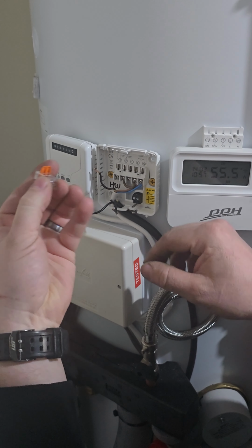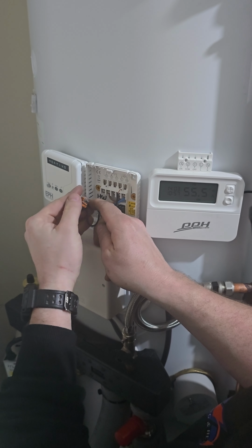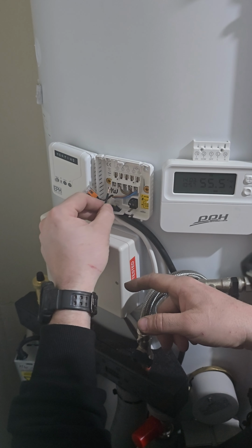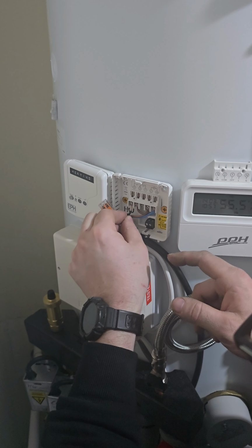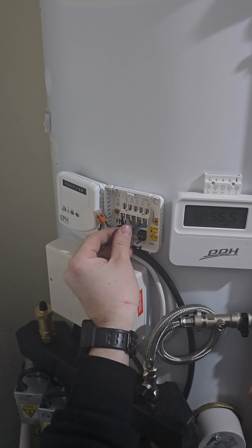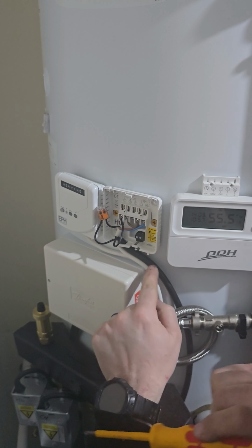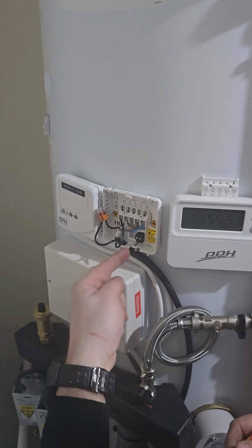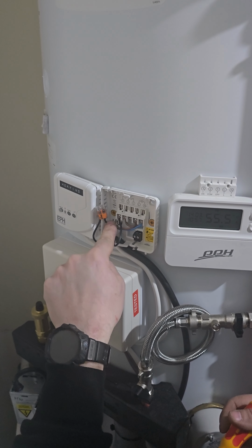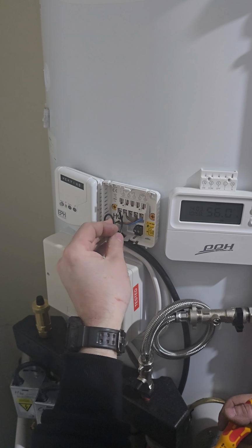So we're just going to get ourselves a cheeky little plumber's push fit, Sparky's push fit, their equivalent, and we're going to link the high limit stat to the switch live out, right, and then we're going to replace the power from the high limit stat back to this. So if the high limit stat activates, even though it's sending power down to the high limit stat through port 3, it won't be coming back from the high limit stat. So it comes power to port 3, down to the high limit stat, back from the high limit stat, back down into the switch live for the zone valve. So if that trips because it's too hot, it'll cut the power to the zone valve and it shuts down. Job is the proverbial good un.